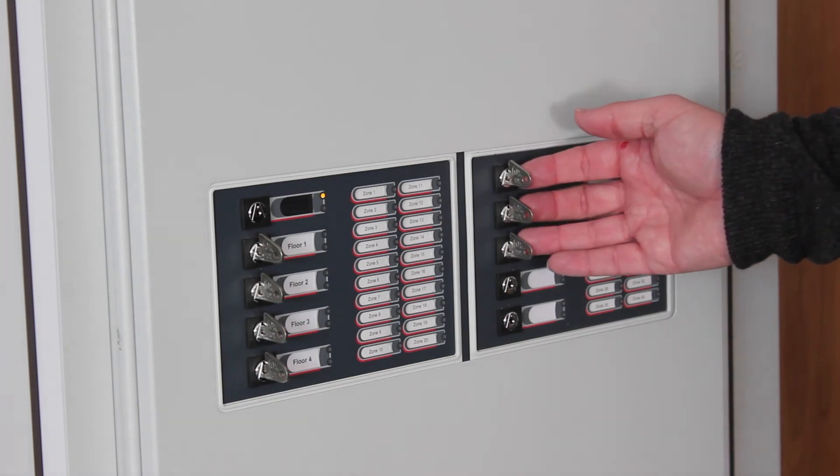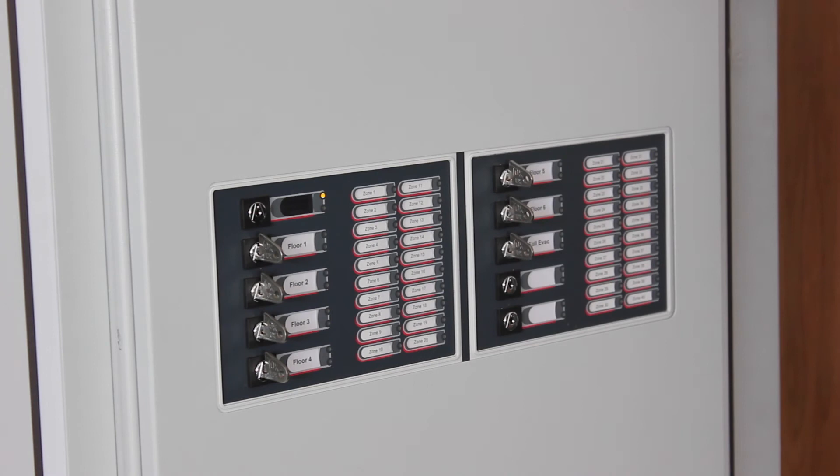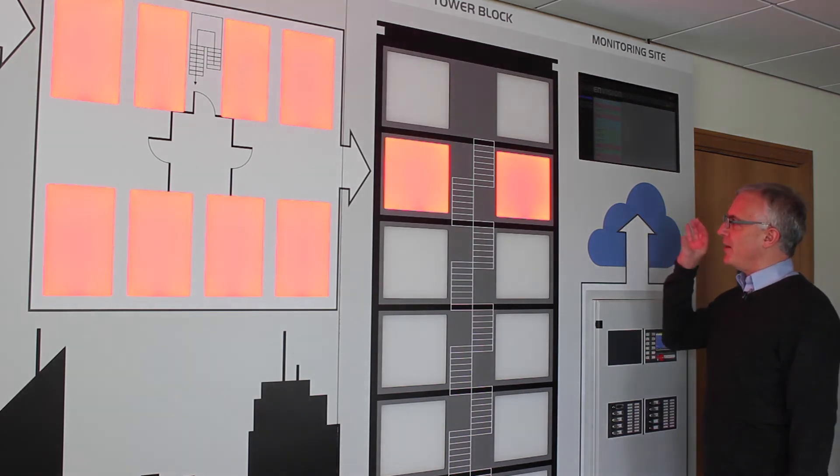So all the panel's key switches are programmed via the ZFP's cause and effects to operate on a floor-by-floor basis. So the fire services have arrived, they realize and know that the fire is on floor 5.